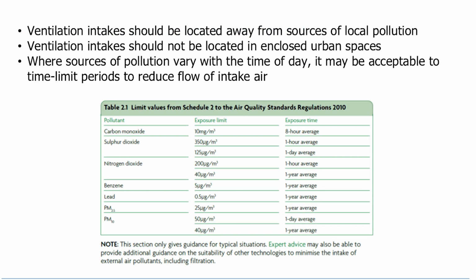Section 2 of approved document Part F states that ventilation systems should be designed to minimise the intake of external air pollutants. In an area of high pollutants, it is likely that this will only be achieved by use of MVHR systems with high-grade filtration.